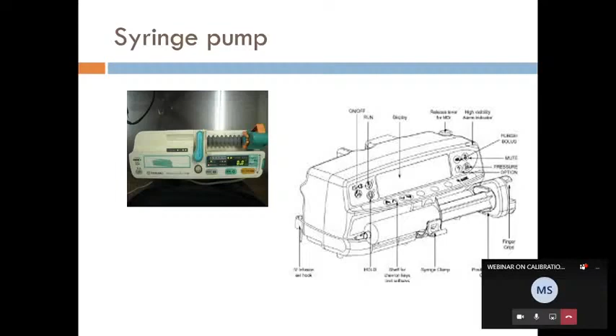In this machine, as soon as you place a syringe, the machine has to acknowledge the syringe. For example, if you place a 50 ml syringe, the machine has to acknowledge and show it as a 50 ml syringe. If not acknowledging, then there may be a problem with a syringe size detection sensor. After placing syringe, if you press the start button and the syringe is not moving, then there may be a problem with a syringe stepper motor or plunger movement problem, okay. With the help of a manual, you can solve the problem, okay.